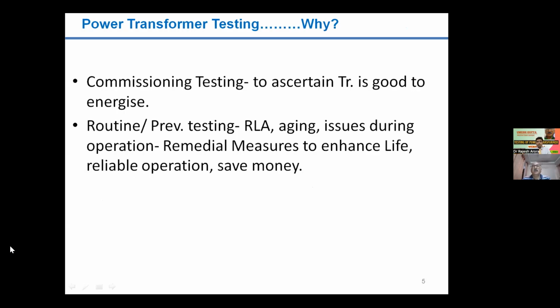So why we need to test the transformer may be classified for the field purpose in two groups. Say one is commissioning testing. It is required to test the transformer to ascertain whether the transformer is good to energize, whether we should put it into operation or not. So there are certain test checks which we do during pre-commissioning, before commissioning of the transformer. Then during its operation lifetime, we do some tests.